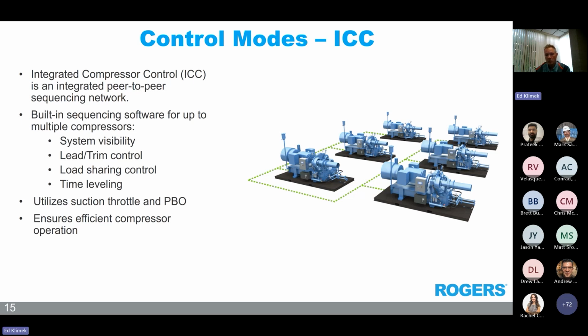The system can network multiple compressors into a single system to ensure efficient and effective operation with multiple compressors within a single header. Some of the advantages of ICC include it provides overall system visibility to ensure that all critical operating data, pressures, temperatures, vibrations can be viewed on any of the networked compressors. Options for both lead, trim, and load sharing exist, and we're going to cover both the lead, trim, and load sharing here shortly. Some of the other options available in ICC are time leveling as well.